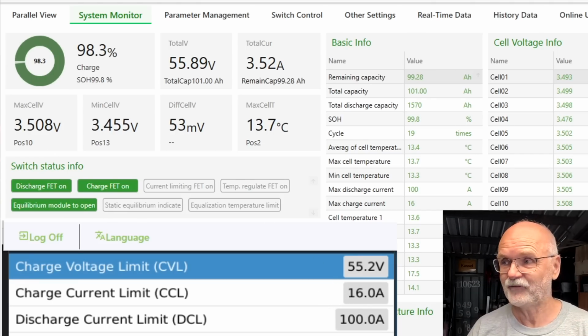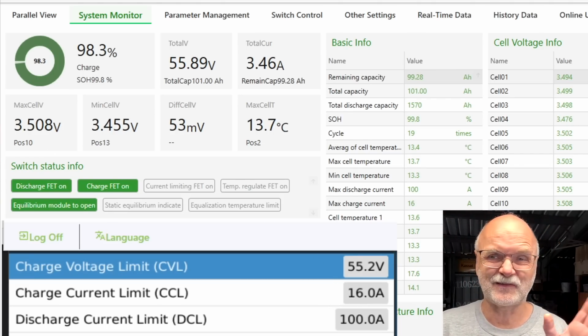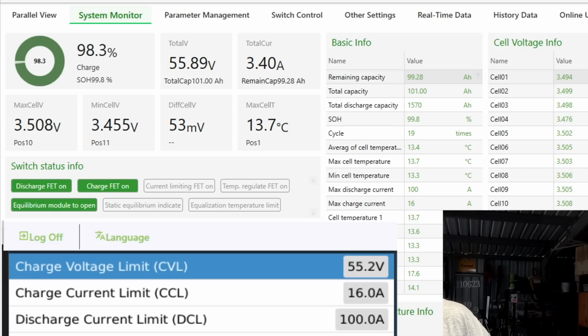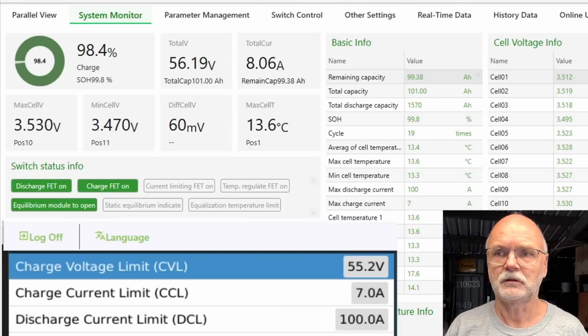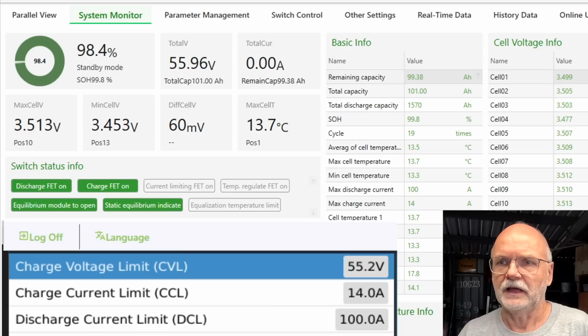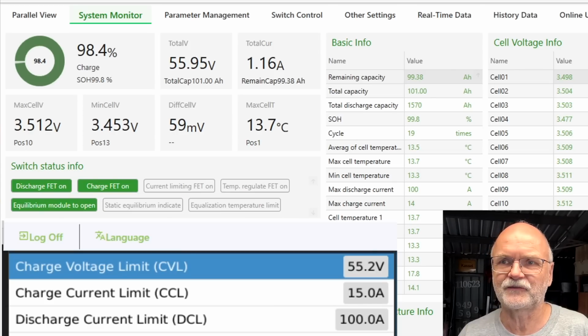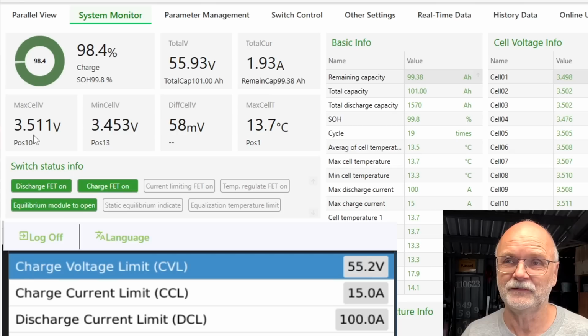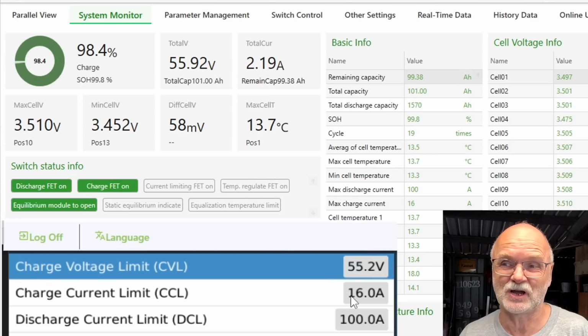And at 3.55, which is 56.8, 56.4... Actually, I'm just going down again to 56 volts, yeah, which is 3.5 per cell, if they would all be balanced. So we can see here 3.51 volts, yeah, which gives us 16 amps of charging current.